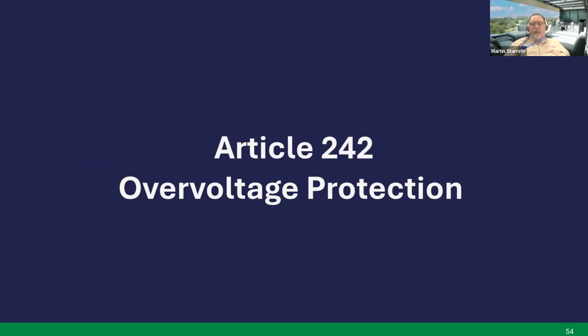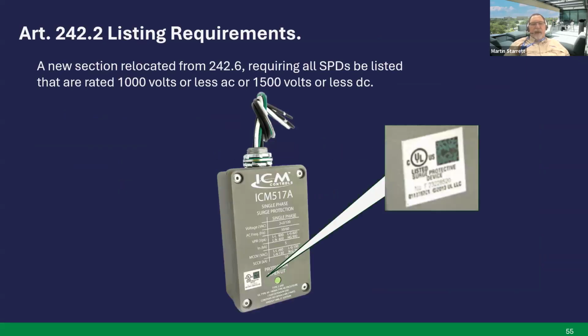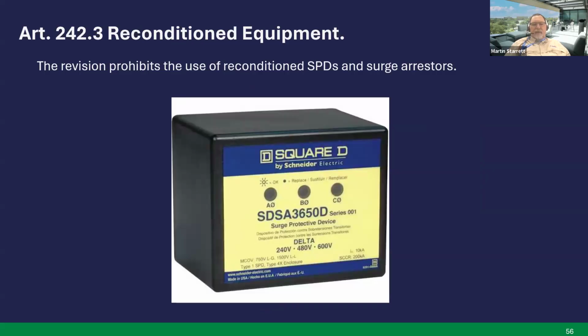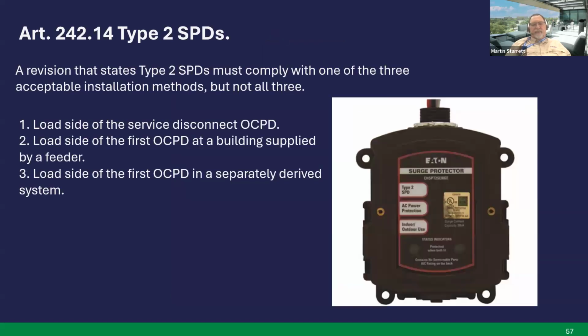Article 242, overvoltage protection. There again, .2, listing requirements, requiring all surge protection devices rated 1,000 volts or less AC or 1,500 volts or less DC to be listed. We'll be seeing a lot of listing; a lot of stuff that was previously required to be listed will be in the 2026. Next slide. There's our reconditioned equipment. The revision prohibits the use of reconditioned surge protection devices and surge arresters. Next slide.